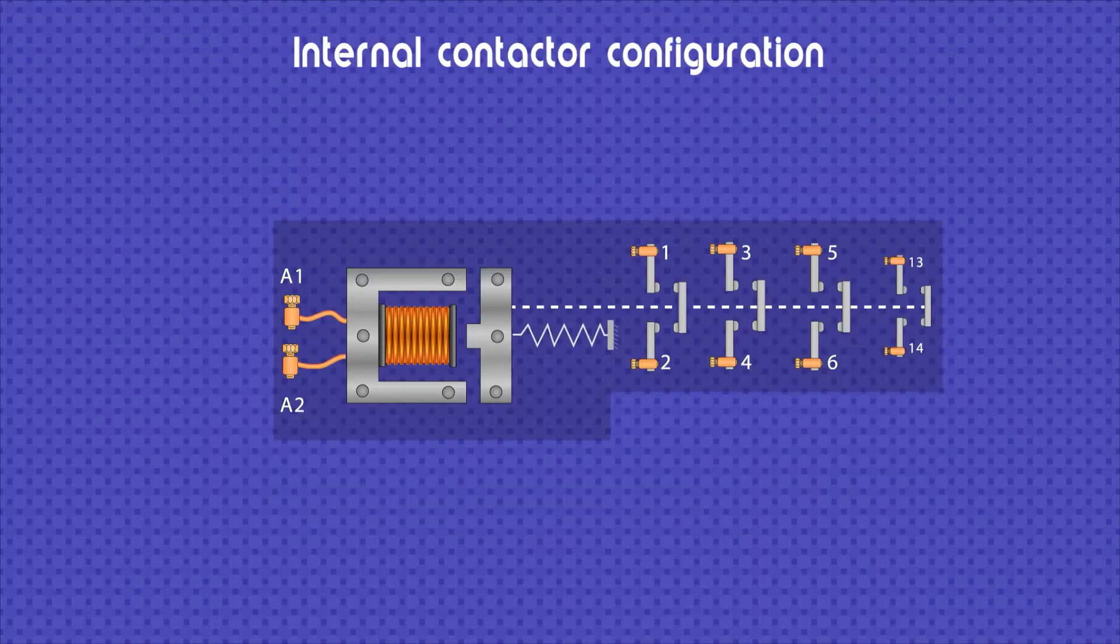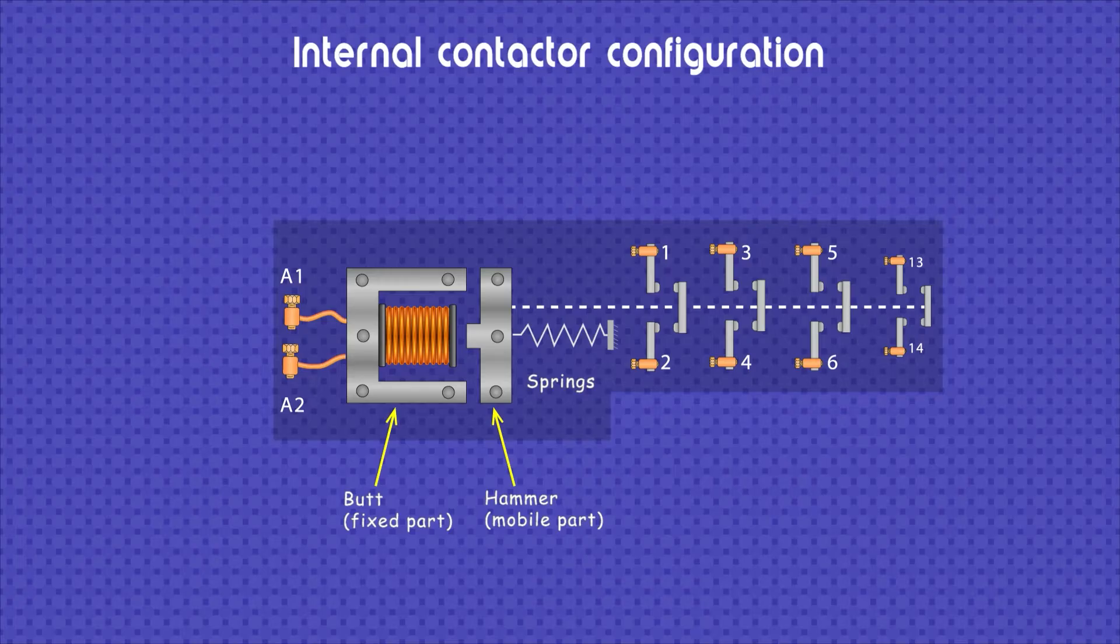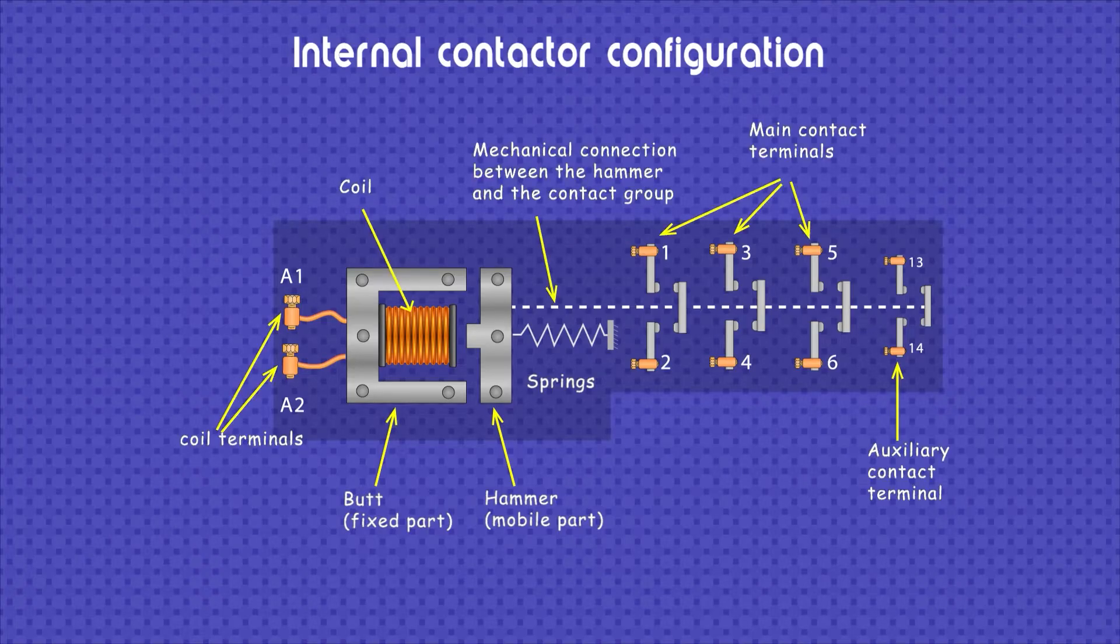Let's now look at the parts and internal configuration of an electromechanical contactor. The butt, which is the fixed part, and the hammer, which is the moving part. These two elements make up the structure of the magnetic circuit when they come together. We also have the coil, which is a coil of wire that, when energized, generates a magnetic field around it along with the magnetic structure described above.